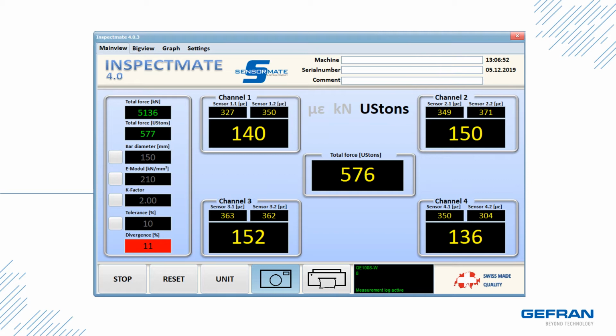This slide is an example of the readings that will be displayed in the SPEC'S software. On the top left-hand side is the total force value, and scrolling down you will see inputs for tie bar diameter in millimeters, Young's modulus, K-factor, and tolerance. Only the tie bar diameter value needs to be entered onto this screen. The other values are set at the factory and do not need to be changed.